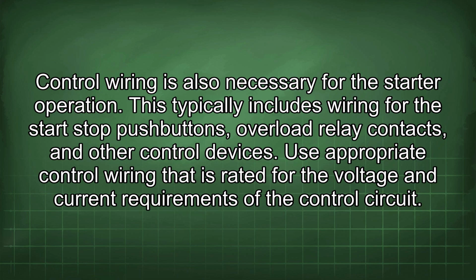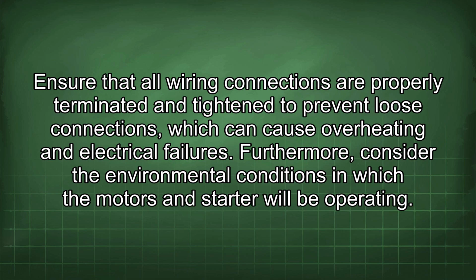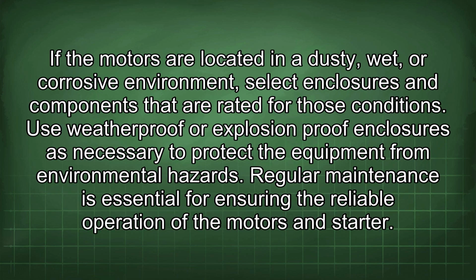Use appropriate control wiring that is rated for the voltage and current requirements of the control circuit. Ensure that all wiring connections are properly terminated and tightened to prevent loose connections, which can cause overheating and electrical failures. Furthermore, consider the environmental conditions in which the motors and starter will be operating. If the motors are located in a dusty, wet, or corrosive environment, select enclosures and components that are rated for those conditions. Use weatherproof or explosion-proof enclosures as necessary to protect the equipment from environmental hazards.